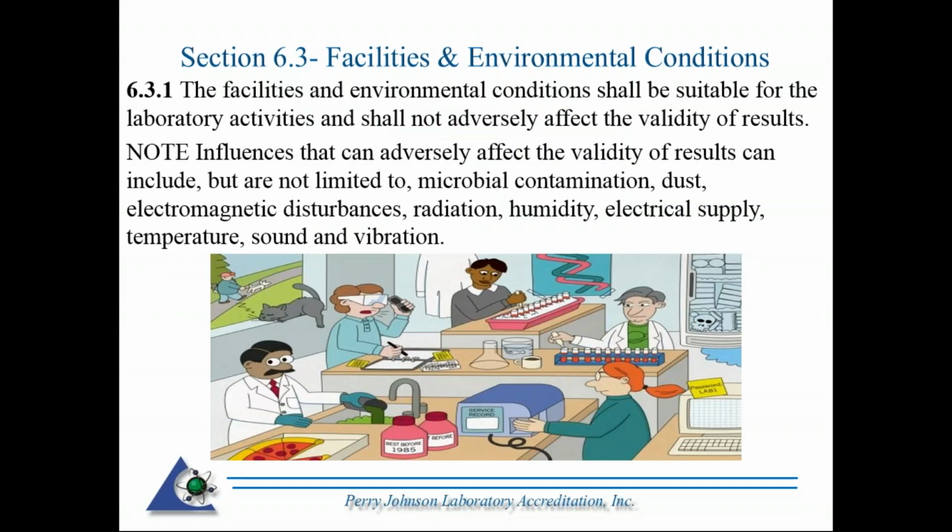So, the very first requirement: the facilities and environmental conditions shall be suitable for the laboratory activities and shall not adversely affect the validity of results. As added information, the standard notes that adverse influences can include, but are not limited to, microbiological contaminations, dust, electromagnetic disturbances, radiation, humidity, electrical supply, sound, temperature, and vibration.